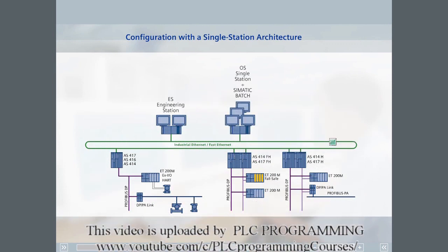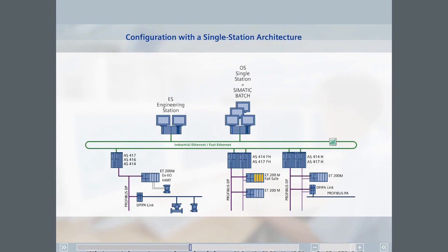The first example illustrates a small system with one engineering station, and a single station on which both OS runtime and batch server and client functionality are installed. The PC should have at least two monitors, so that there is enough screen space to be able to control and monitor the batch control center, batch CC, and the OS at the same time.